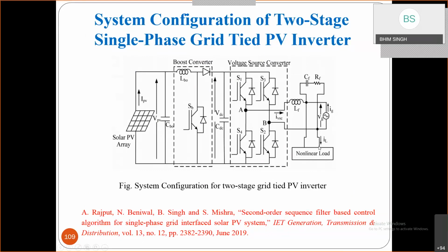In India, our voltage fluctuates over a wide range. If we keep the DC link voltage in coordination with AC voltage, we are able to reduce losses by 3 to 4% in the inverter, while the increase in losses elsewhere was only 1.5 to 2%. So overall generation increased by a couple of percent on this side.